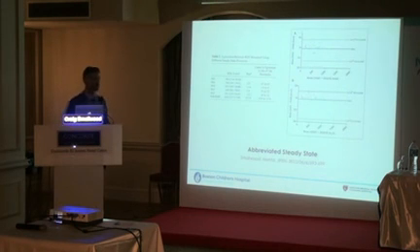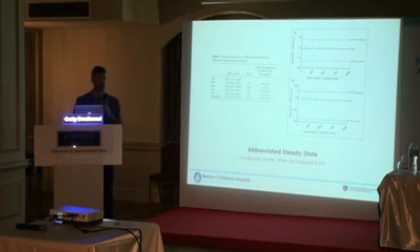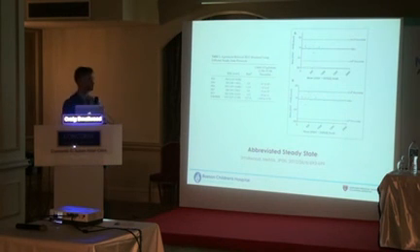One of the things that really is a difficulty in the NICU and PICU is when you apply the device, you bring in the indirect calorimeter, the technician sets everything up, you get a good test, you think that you have good results, you go back to the lab and run the statistical process to ensure steady state, and there's no steady state. So it means your test is invalid. Basically, we wouldn't suggest in that context that that number be transmitted to you guys, the physicians, to make decisions about nutrition, and it was all basically for naught, and we'd also want to do another test.